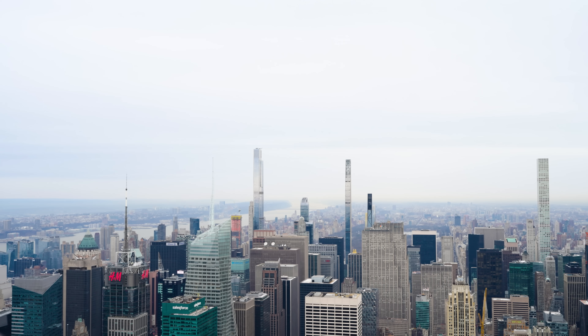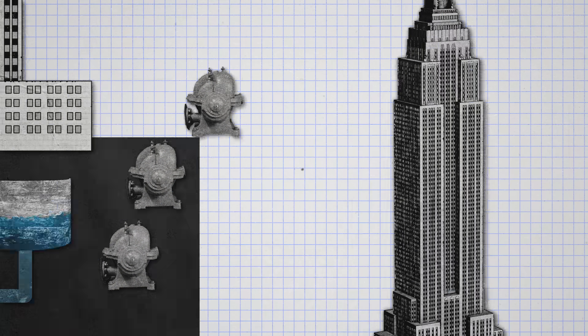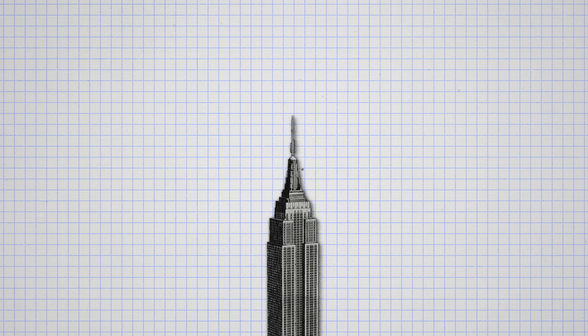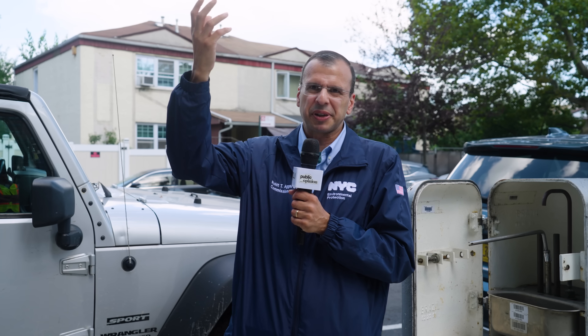Hi, my name is Tim Daly. I'm the director of engineering for the Empire State Building. I've been on the job here for nine years. So how does water get to the top of a skyscraper in New York City? We have a holding tank in the lower level of the building that feeds a series of pumps. Because the building is so high, we have three zones of pumps: low, mid, and high zones. The top tank is on floor 101, and the water is basically gravity fed down through the six tanks in the building. Above about six stories, you need some artificial pressure within the building.